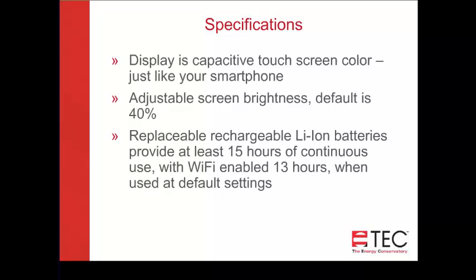But we also know that given our current technology with the batteries that we're planning to use, the replaceable rechargeable lithium-ion batteries will provide at least 15 hours of continuous use. And even with the Wi-Fi enabled, you're going to get 13 hours. So we think that this is truly a great working instrument. We've also done drop testing. A lot of people have looked at that display and said, oh, that can't be very durable, and the case can't be very durable. Well, the case itself is a far better plastic material than the DG-700, and we've done drop testing to 5 feet, and it's really a solid device.